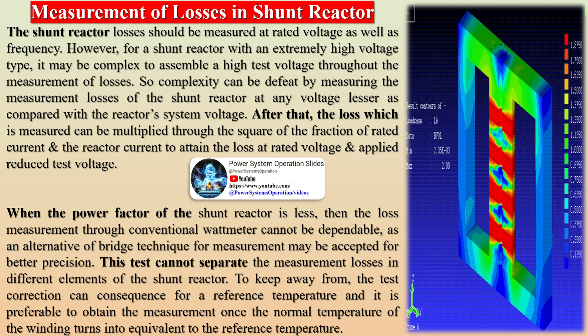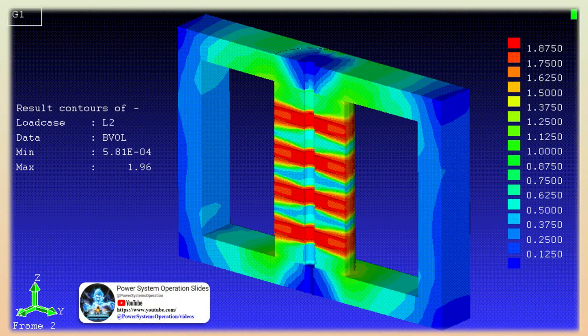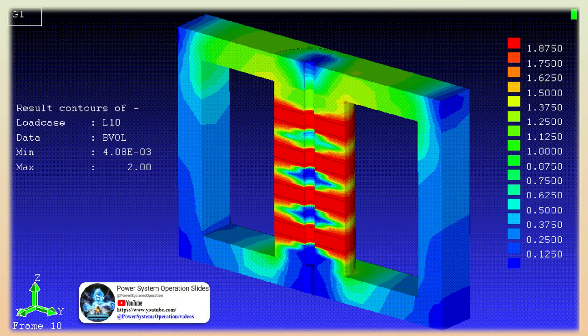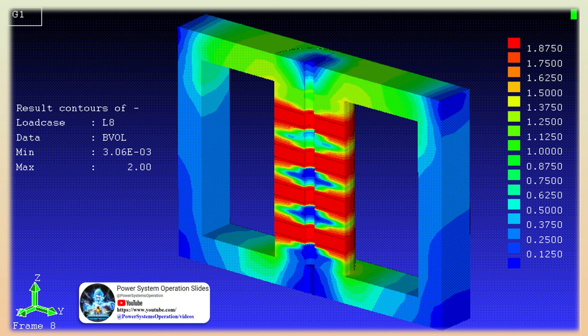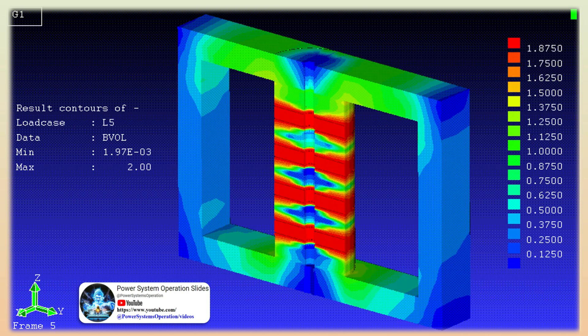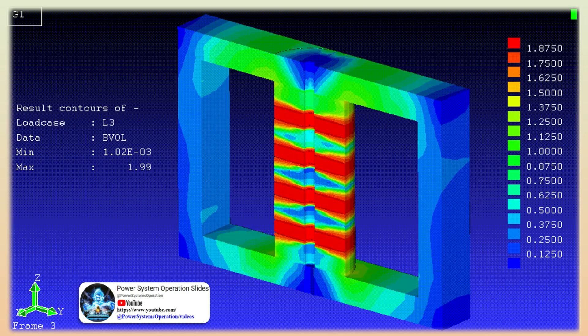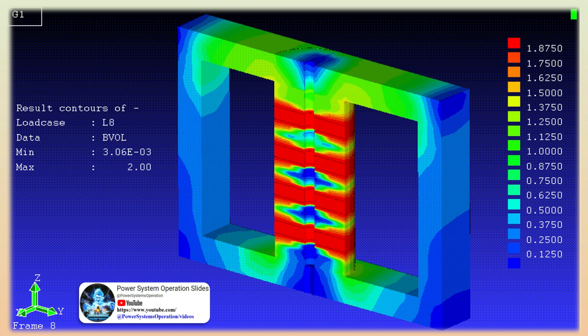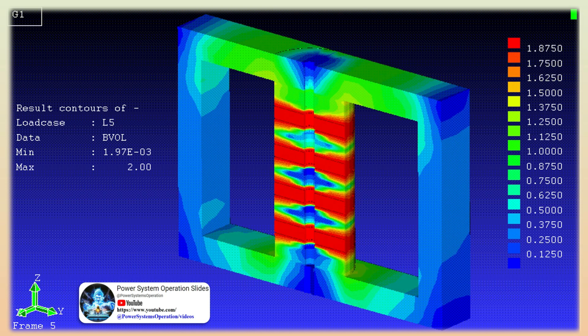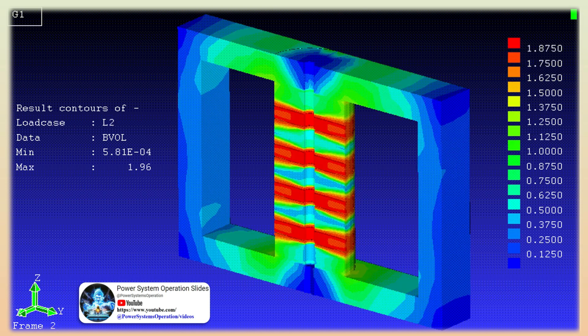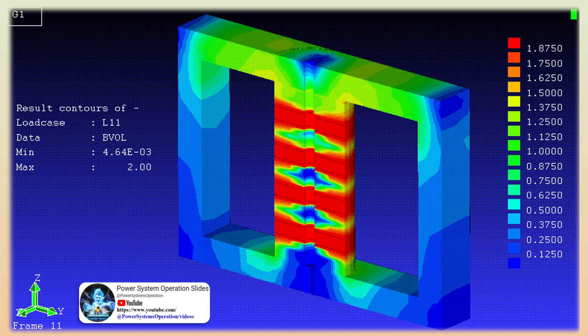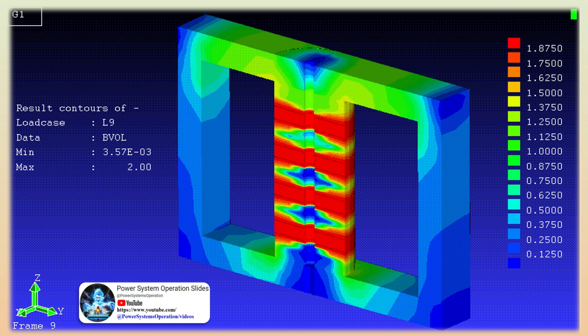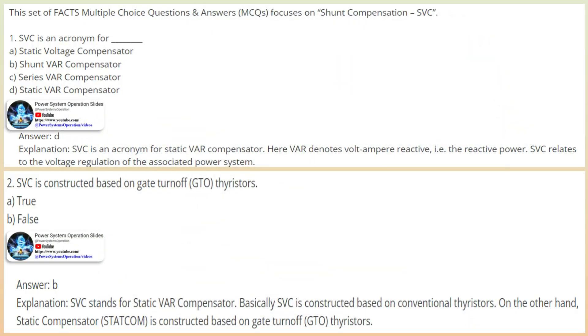These classifications help in selecting the right type of shunt reactor for specific applications, ensuring efficient and reliable operation of power systems. Regarding reactor earthing: the neutral of the reactor is grounded to provide a return path for fault or unbalanced currents, typically using two separately treated earth pits. To prevent heating of the tank due to eddy currents caused by voltage buildup, the tank's potential is kept at zero by connecting it to the earth grid.